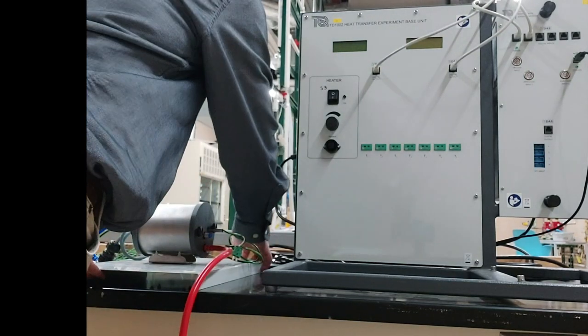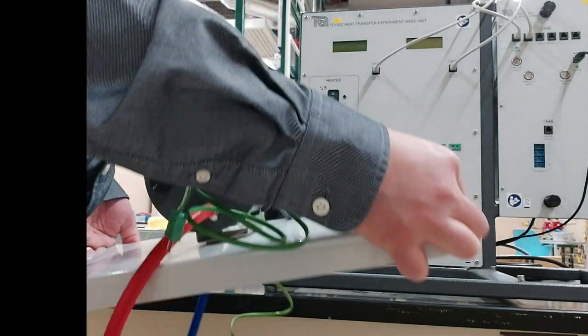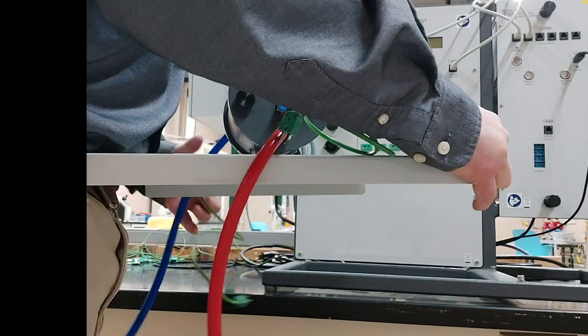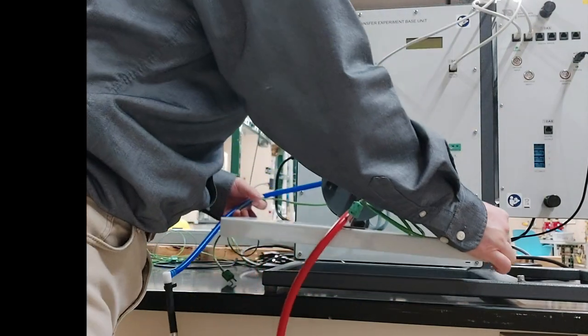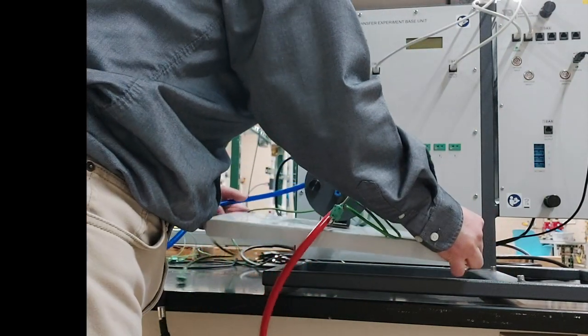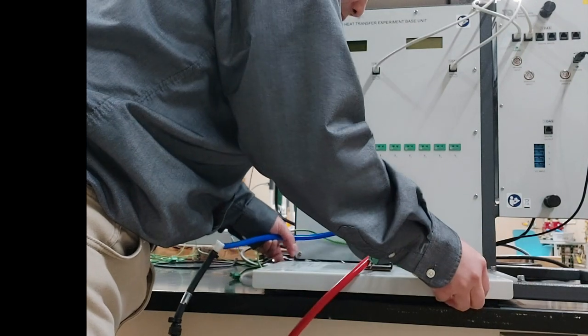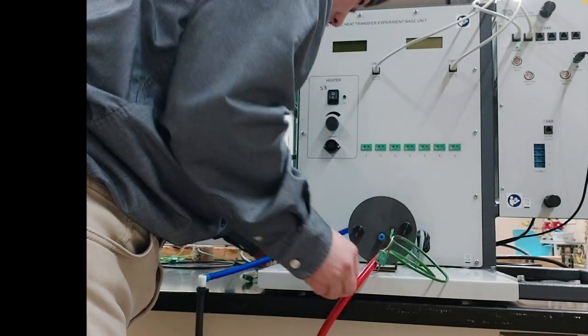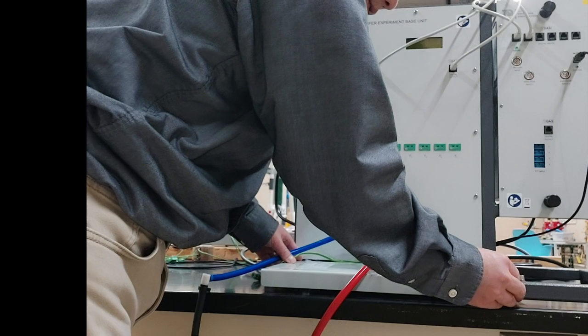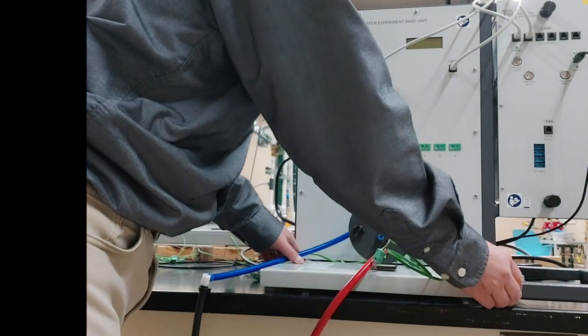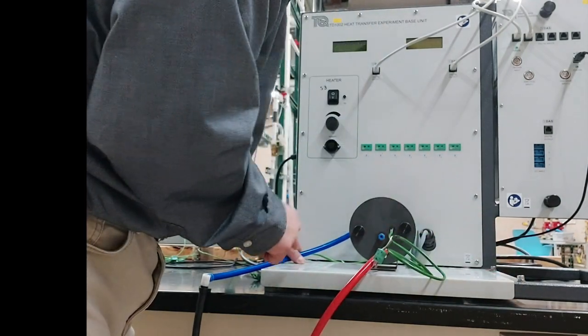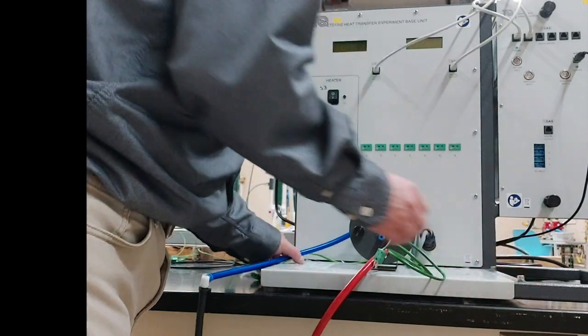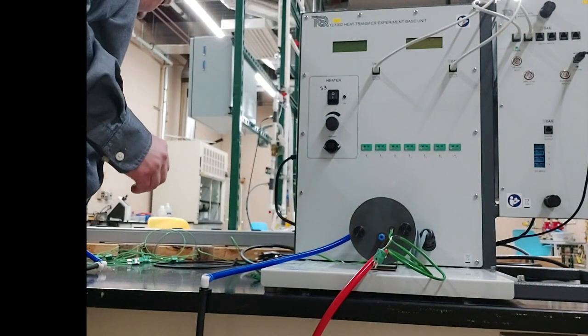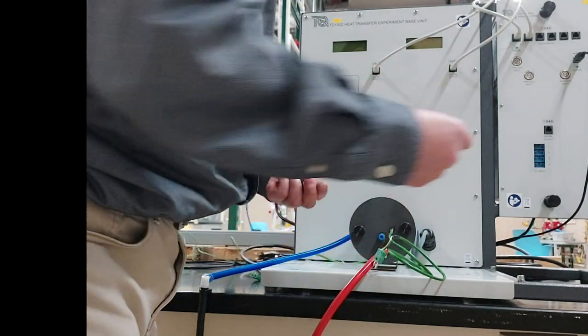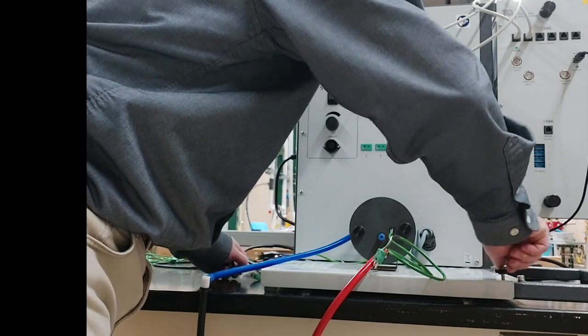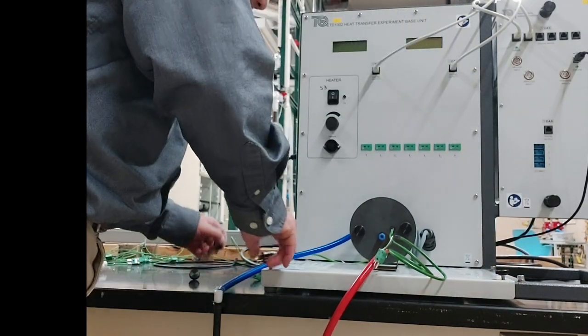Then it's time to bring in the gas thermal conductivity module. Set it gently on the gray metal frame of the instrument. Move it to the right place without pinching any of the wires and tubes. Make sure the base screw holes are aligned and use 4 screws to fix the new module's base to the gray metal frame of the instrument.